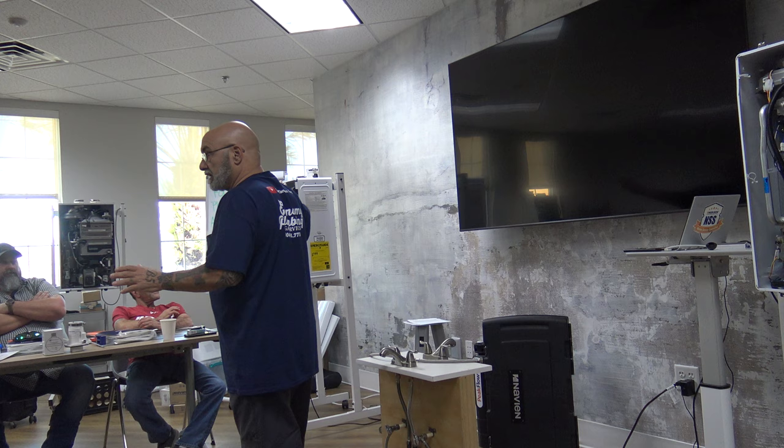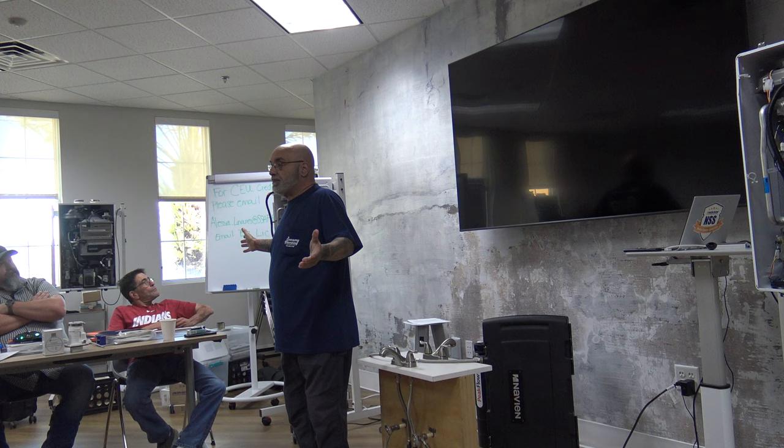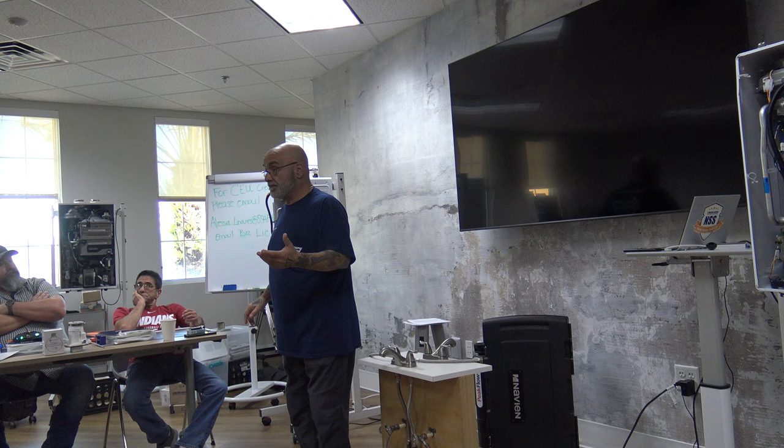And I can show you hundreds of pictures that people have sent me of a 2-month-old Rinnai vented with dryer vent into the B vent. Nice. Again, manual. It tells you. Venting this thing properly, whether it's this unit, which is fairly easy, it's PVC pipe, Schedule 40 DWV fittings. Glue it, pitch it and follow the way they show you.